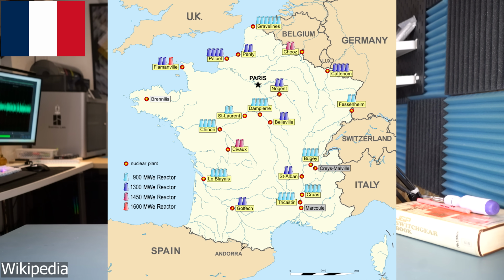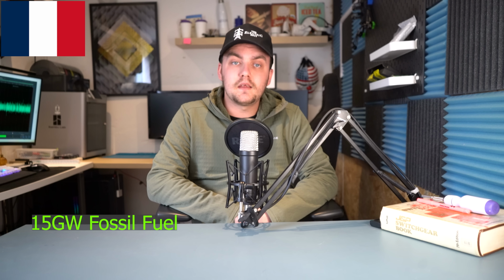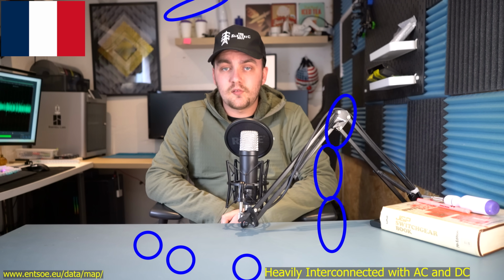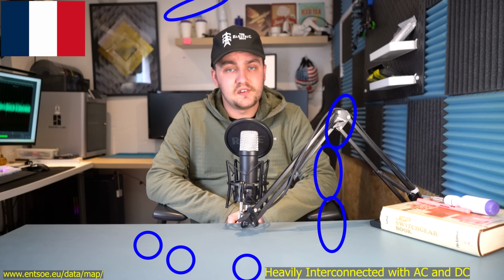France, which was also affected by the blackout, is a unique case, because between 40 and 60% of its electricity comes from nuclear, and while nuclear plants usually scram during a blackout, some are capable of operating in island mode, meaning they can keep powering their own systems or nearby load, ready to reconnect once the grid is stable. France also has around 25 gigawatts of hydro and 15 gigawatts of fossil generation to support Black Start, plus around 23 gigawatts each of wind and solar, and because it's so well connected to the other European grids, interconnectors often play a key role in restarting parts of the French system, assuming the neighbours aren't down too.